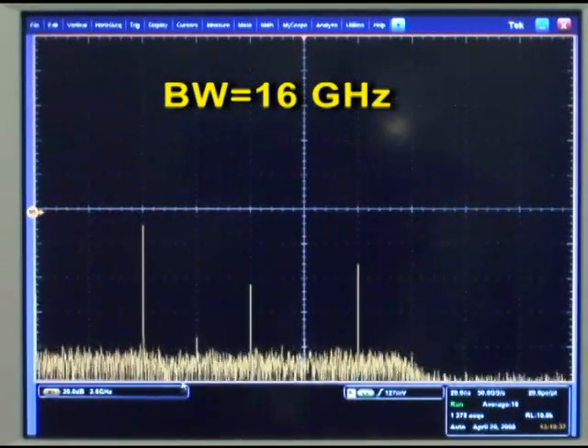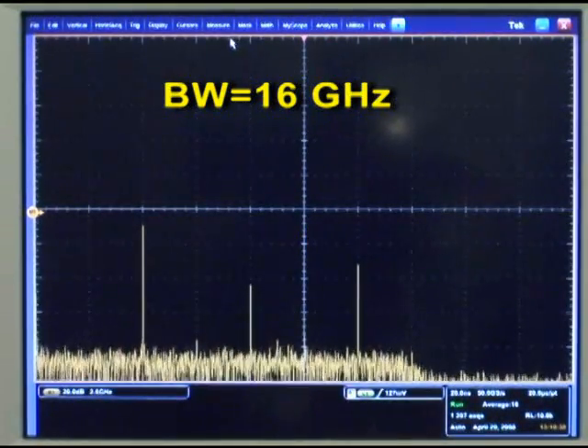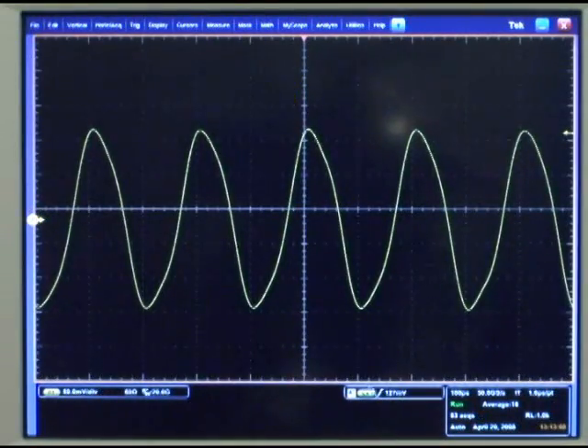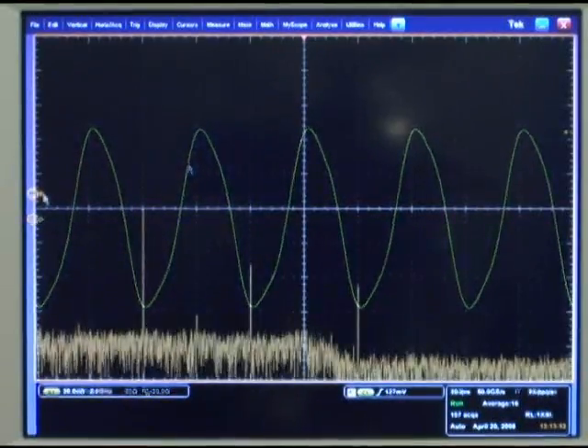The point being, without the DSA 70,000's extra bandwidth to capture those important frequency components, this signal will not show its true shape. To illustrate this point, let's turn the bandwidth of the DSA 70,000 series back down to 13 GHz.